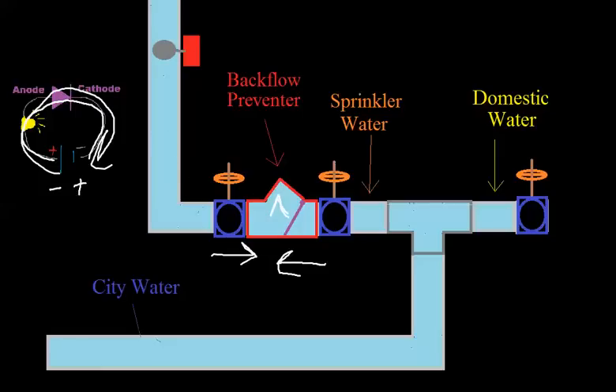Well, if somebody had shut this off and the system was not full, there was no water in the system, or even if there were water in it, once a sprinkler had broke, if one of these valves was shut, you'd only have the water available in the system. And once that was gone, well, first of all, there'd be no pressure. Second of all, you wouldn't have enough to put out the fire. So the idea is you have to know when someone's shutting off these valves.